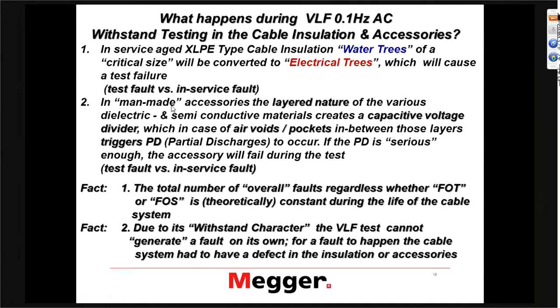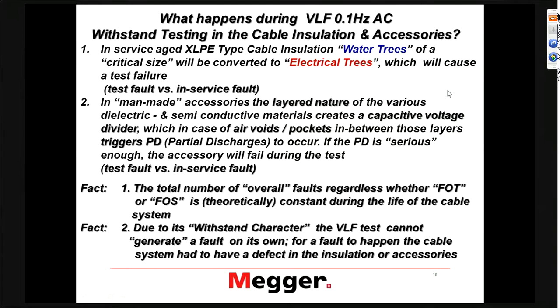What happens with accessories — what I call manmade accessories — is they are layered in nature because they have different types of materials. These different type materials have different dielectric properties, which create basically a voltage divider across this insulation. If you have air pockets in it — that's really the issue — because typically the field in the air pocket exceeds the breakdown voltage of air and you get partial discharge.